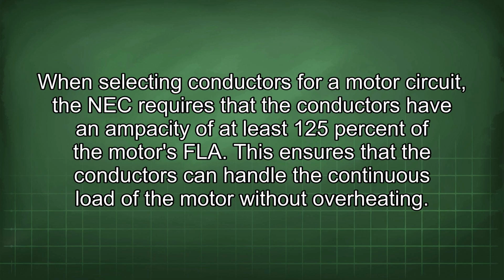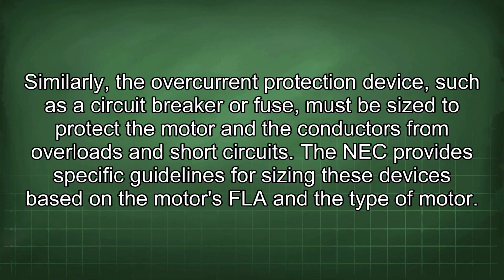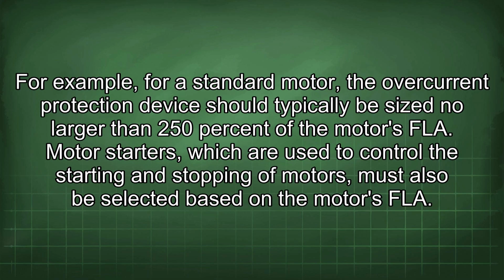When selecting conductors for a motor circuit, the NEC requires that the conductors have an ampacity of at least 125% of the motor's FLA. This ensures that the conductors can handle the continuous load of the motor without overheating. Similarly, the overcurrent protection device, such as a circuit breaker or fuse, must be sized to protect the motor and the conductors from overloads and short circuits. The NEC provides specific guidelines for sizing these devices based on the motor's FLA and the type of motor. For example, for a standard motor, the overcurrent protection device should typically be sized no larger than 250% of the motor's FLA.